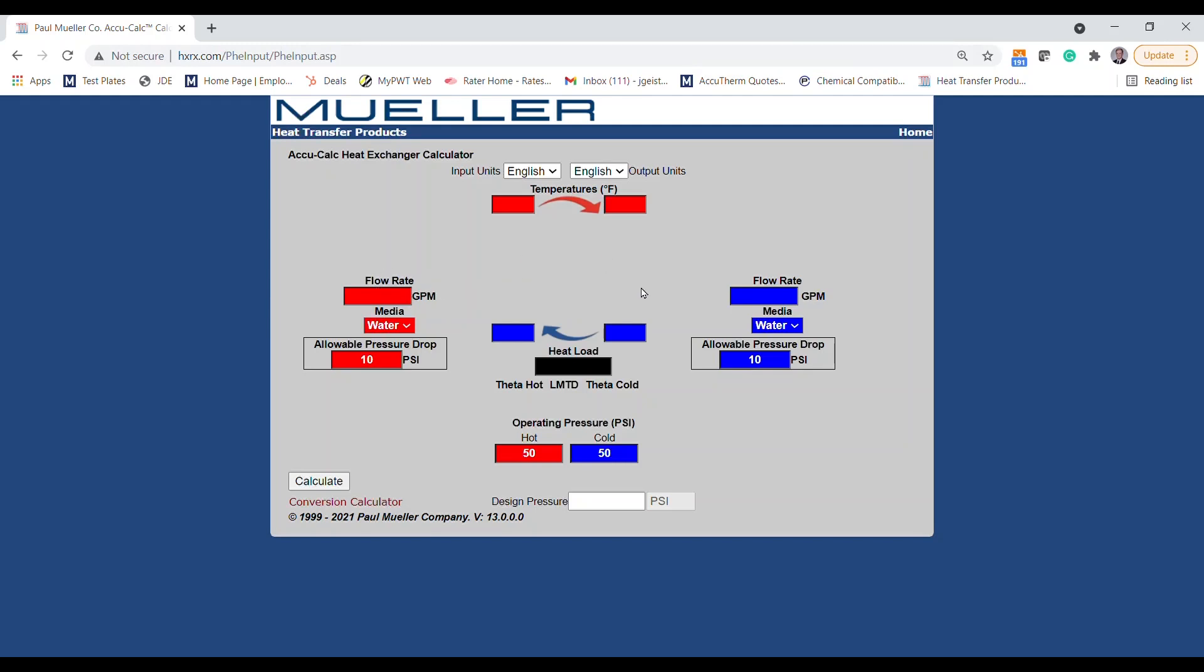Typically, you'll have a load fluid whose parameters are more critical and a service fluid whose properties are more malleable based on what the facility will have available. Generally, you will want to enter the load side flow rate, entering temperature, and desired temperature out. Then you want to enter the service fluid properties.